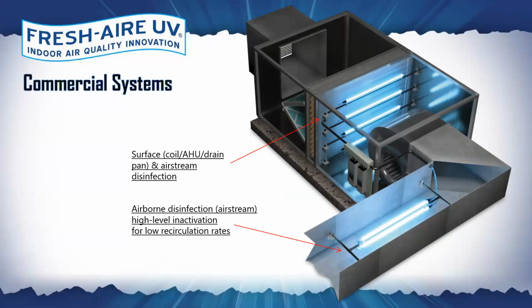Essentially, it creates a field of UV in the ductwork, so as the contaminant passes through this field, there's an extended amount of contact or dwell time between the UV field and the contaminant. If the duct is very large or if the air is moving very fast, we might need 2 of these in series or in parallel. But the design of the system is to deliver the most possible UV irradiance over the shortest period of time. And these types of systems are our go-to solution, our strategy, for those applications that require very high log reduction with very low recirculation.